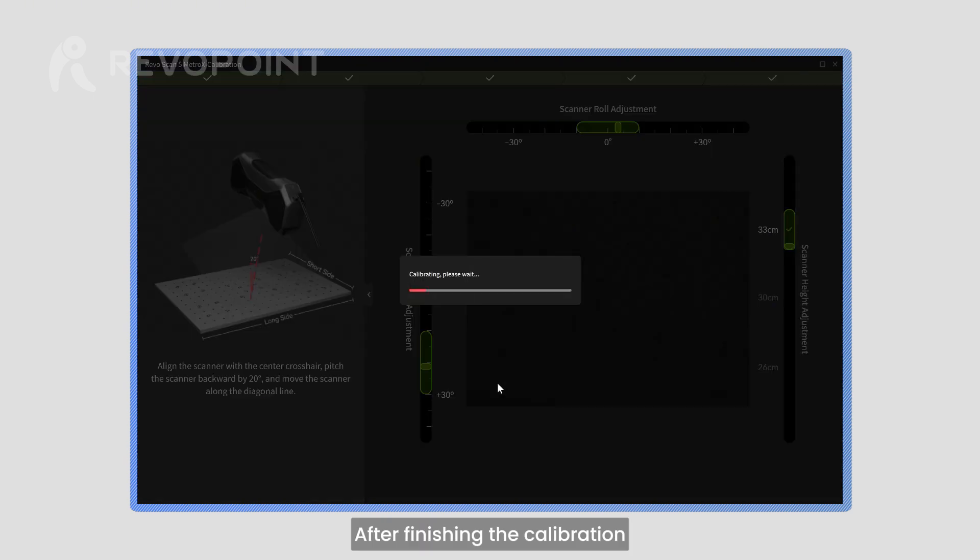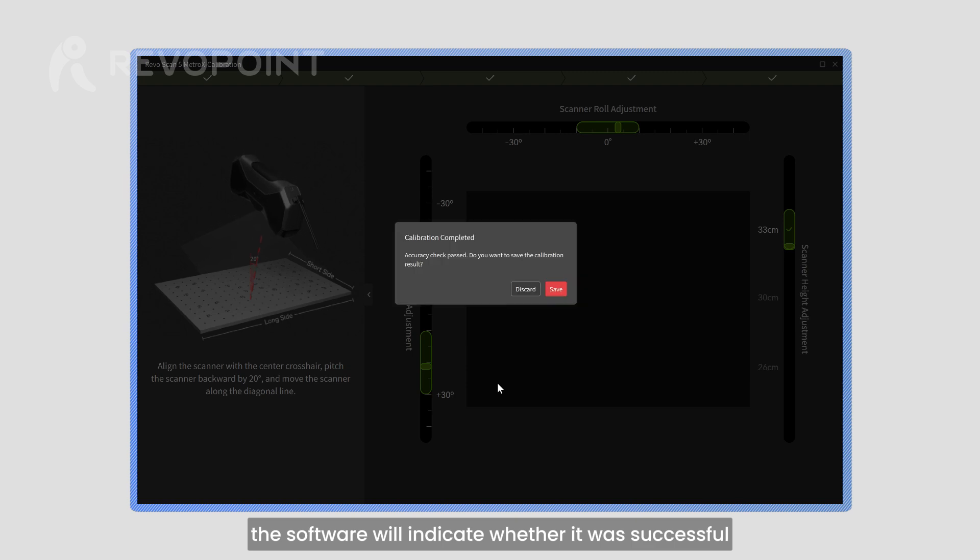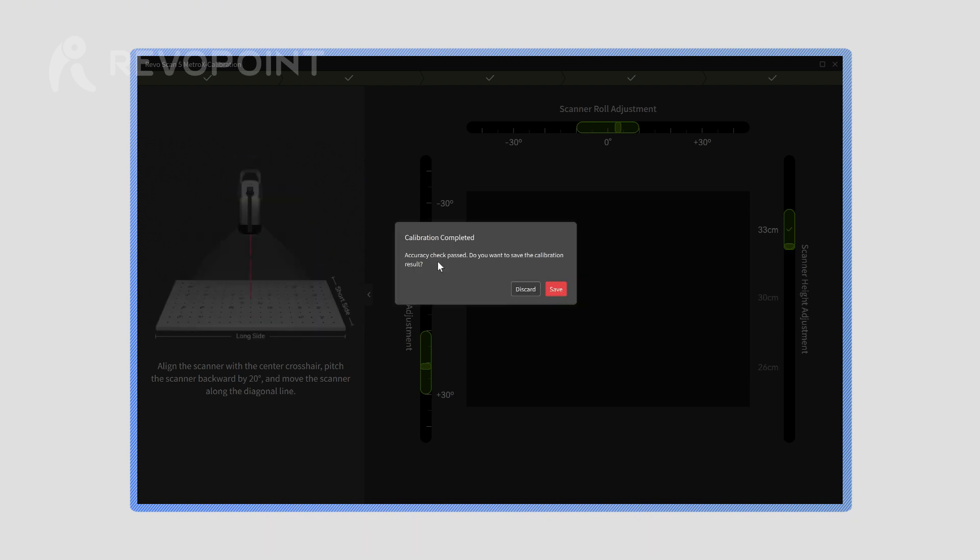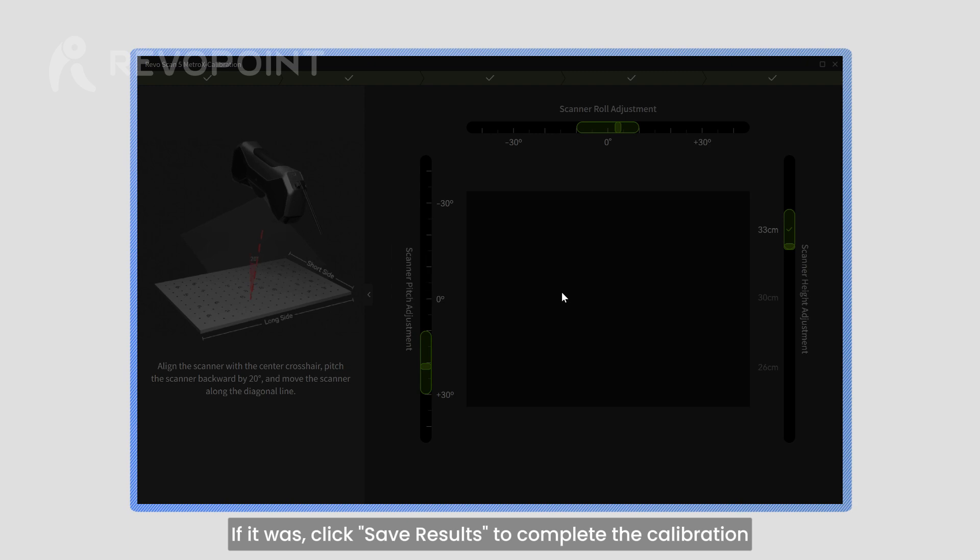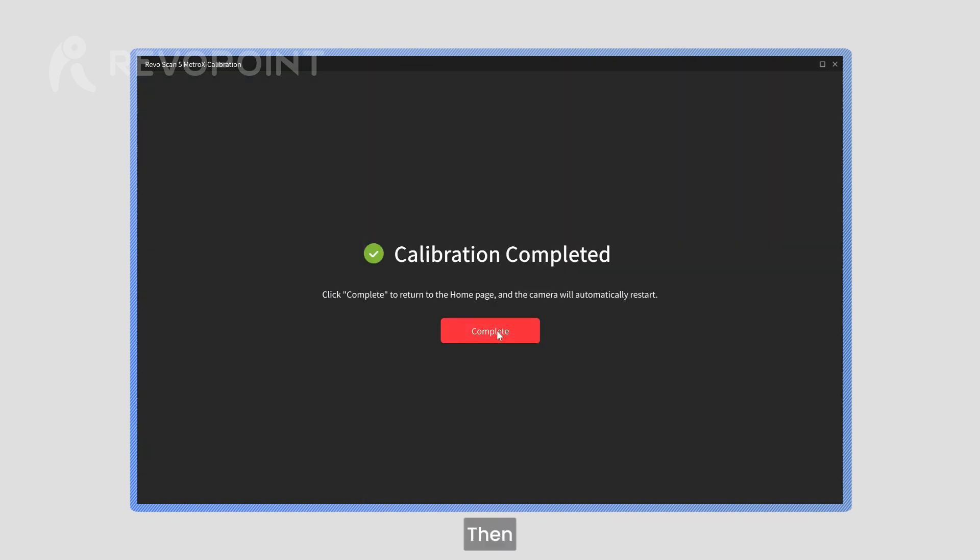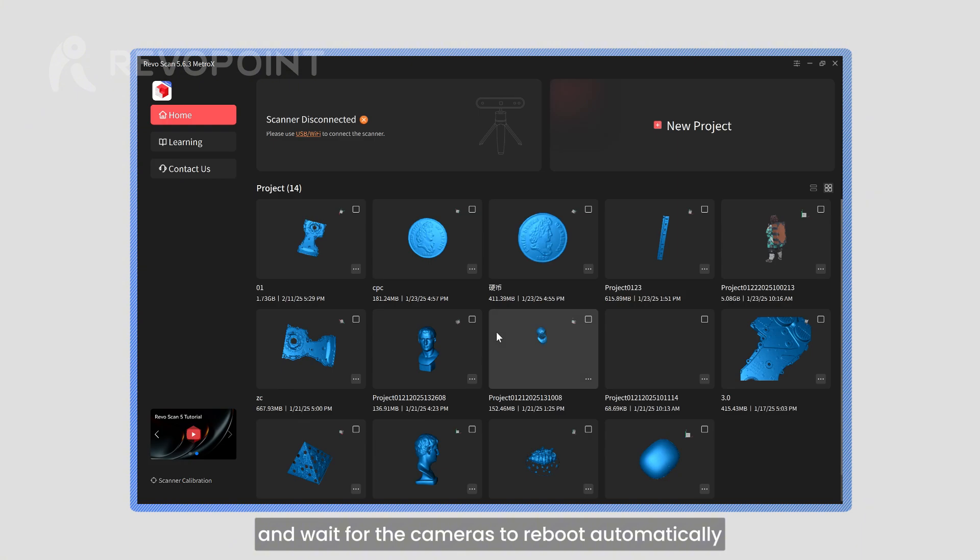After finishing the calibration, the software will indicate whether it was successful. If it was, click Save Results to complete the calibration. Then, click Complete to return to the home page and wait for the cameras to reboot automatically.